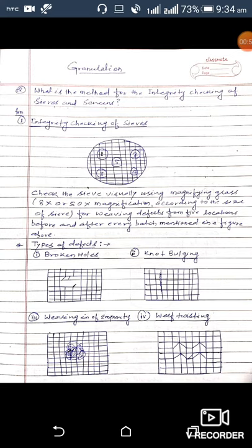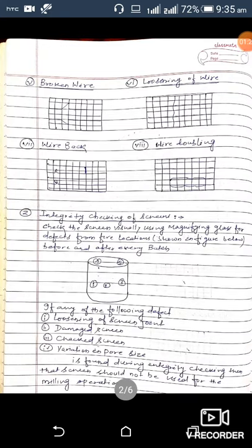The next point is types of defects. There are several types of defects observed during integrity checking of sieves. Examples include: broken holes, bulging, weaving, inclusion of impurity, twisting, broken wire, loosening of wire, wire back, and wire doubling, etc.